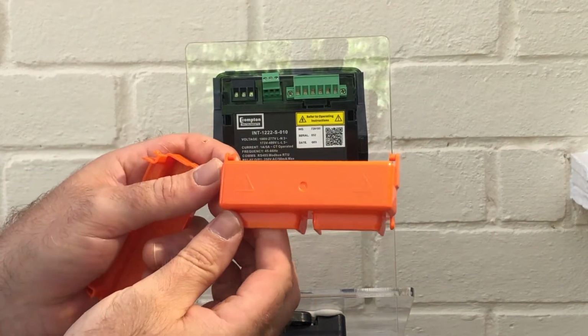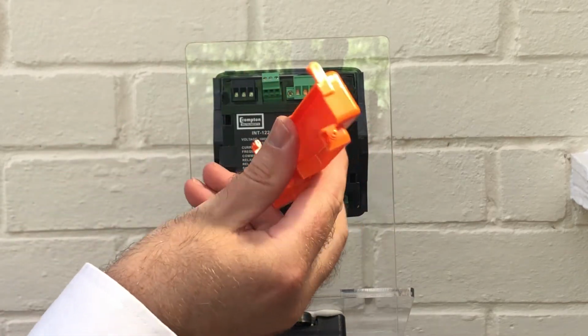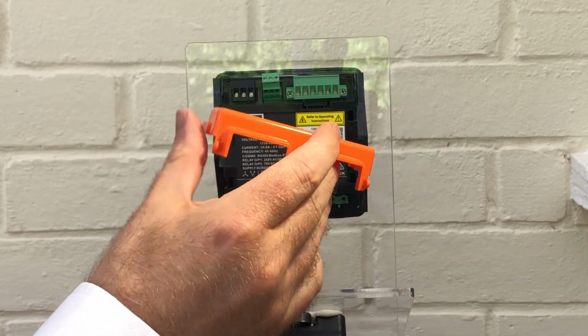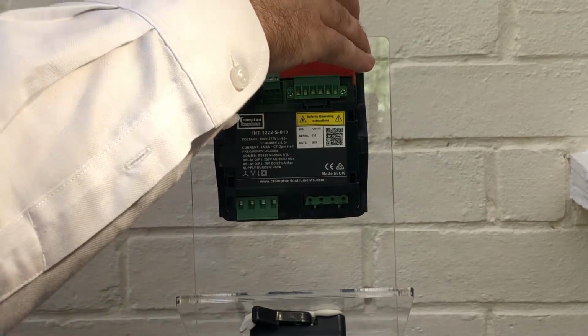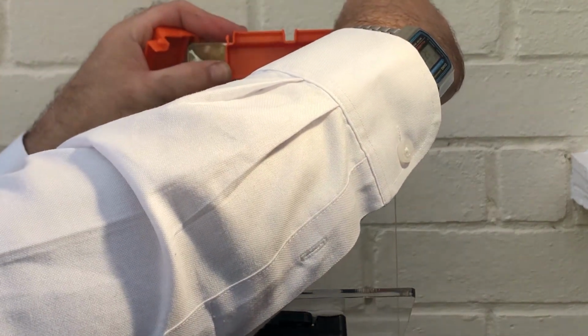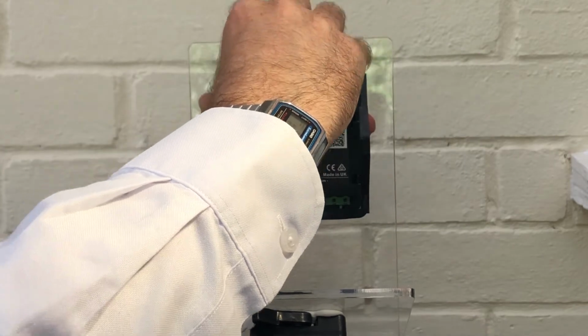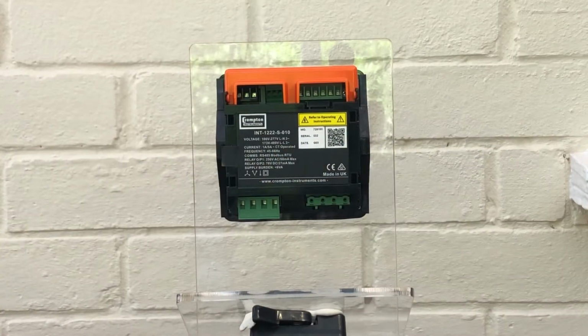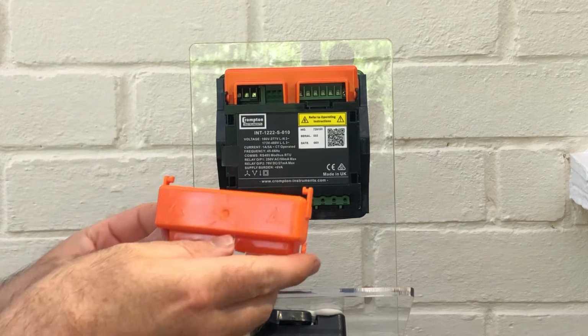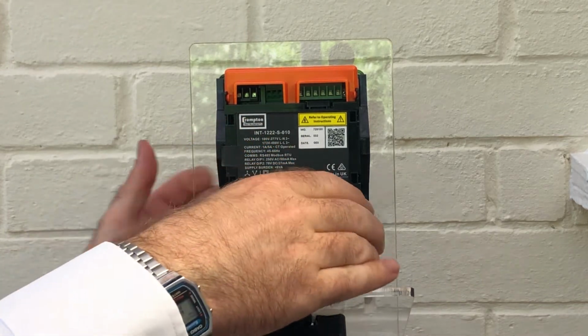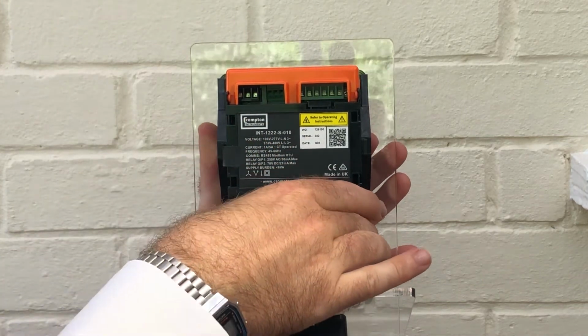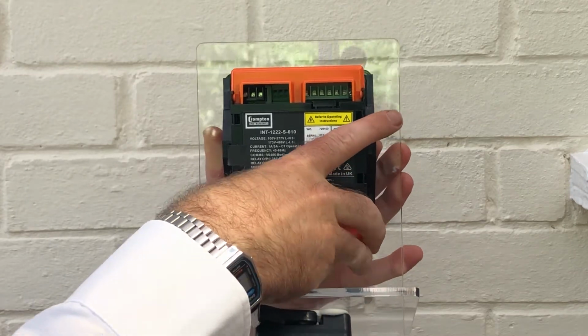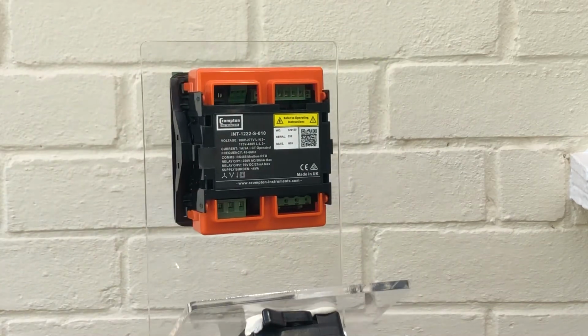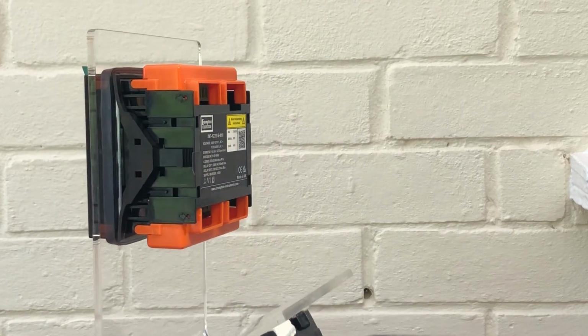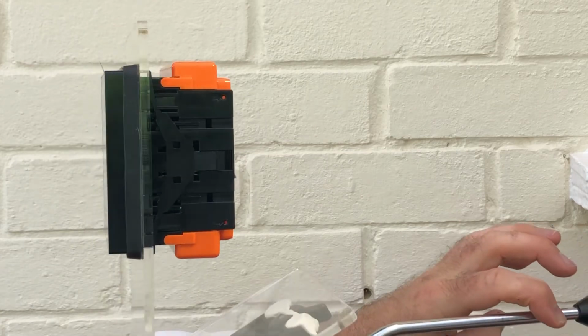Next, we're going to apply the wire sealable terminal covers. As you can see, there are 2 pips, one either side of the terminal cover, which slide into the slots on the top. Simply press forward and shut down the terminal cover. Repeat this process for the bottom terminal cover, which slides into place exactly the same. That completes the hardware setup for the Integra 1222 self-powered unit.